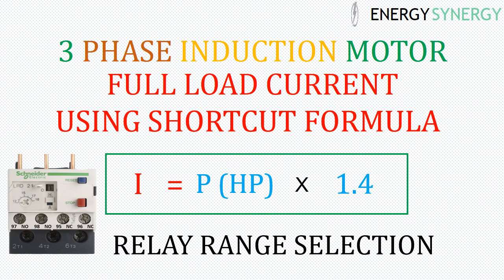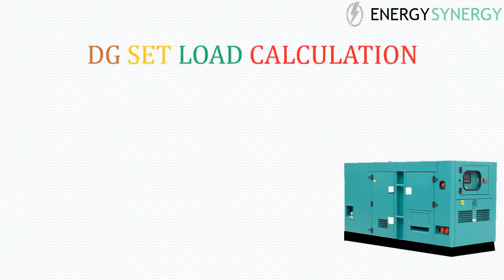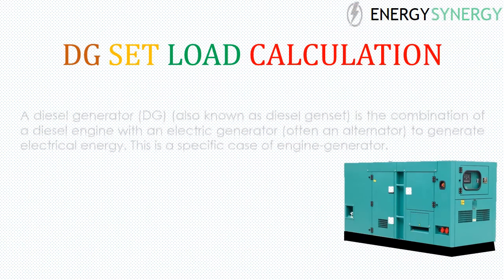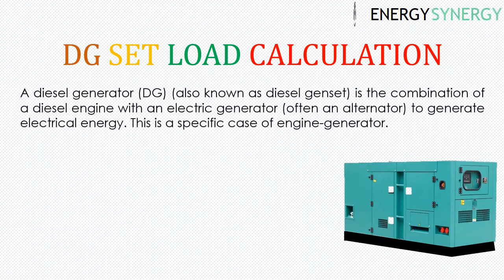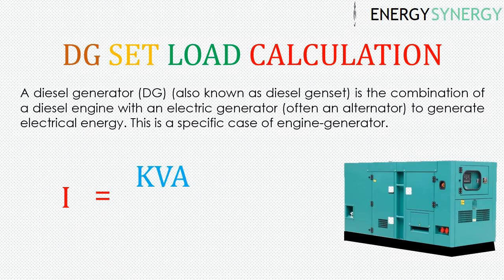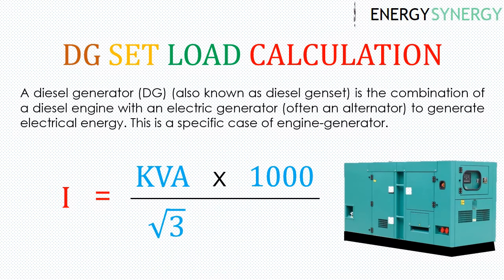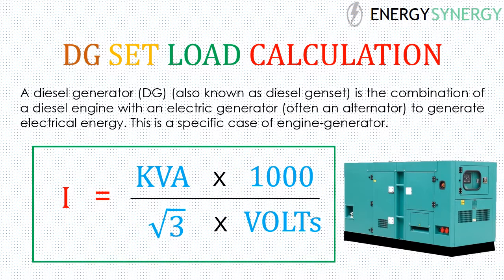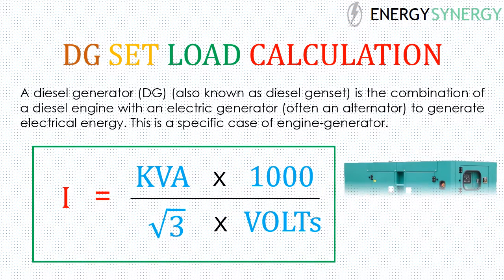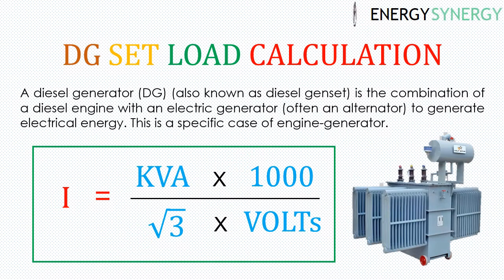This doesn't mean the formula is incorrect — it will give you a good idea of the motor's full load current. Next comes DG set load calculations. A diesel generator, also known as a diesel genset, is the combination of a diesel engine with an electric generator to generate electrical energy. The formula for calculation of load is: kVA × 1000 / (√3 × V). This formula is also used to calculate the current of a three-phase transformer.